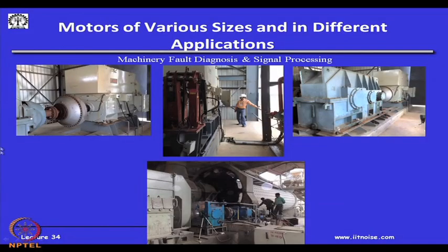And this is used to drive a conveyor system, and you can see the dimension. My technician is standing here, and you can see how big this motor is compared to the person. This is another view of this motor, which is driving a multi-stage gearbox. In fact, you can see three shafts here, 1, 2, 3, and you can see the direction. It is a 90-degree arrangement, a bevel gear arrangement. Power is coming in this direction, and then power is going out in this direction. And you will see these motors and machines are well maintained. The alignment has to be perfect. Otherwise, if there is a misalignment, the rotor at one end of the motor is going to have an excessive force, and the bearing at one end may get damaged.